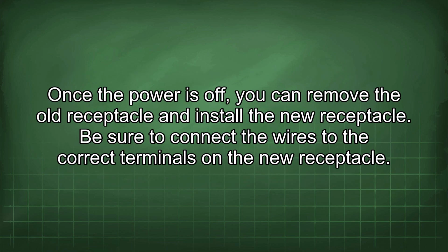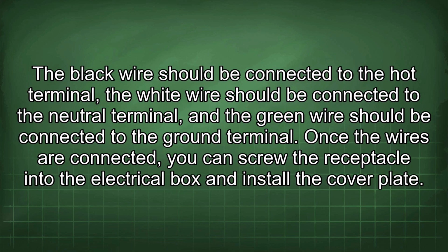Once the power is off, you can remove the old receptacle and install the new receptacle. Be sure to connect the wires to the correct terminals on the new receptacle. The black wire should be connected to the hot terminal, the white wire should be connected to the neutral terminal, and the green wire should be connected to the ground terminal. Once the wires are connected, you can screw the receptacle into the electrical box and install the cover plate.